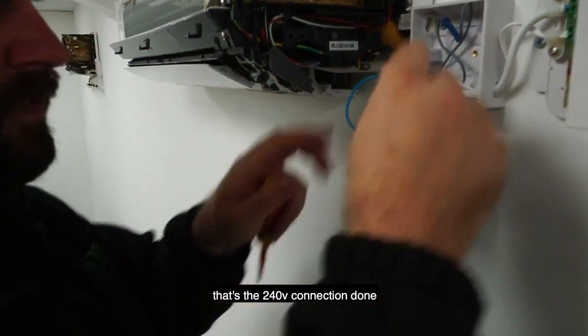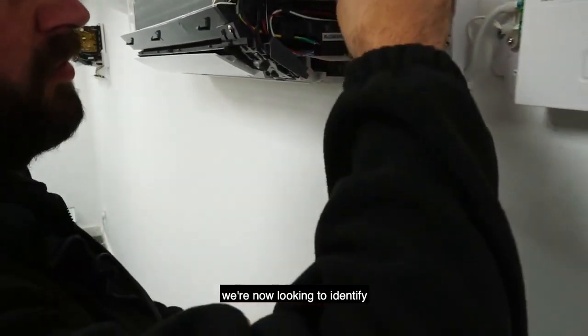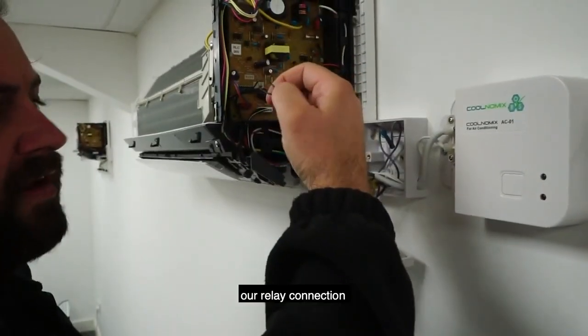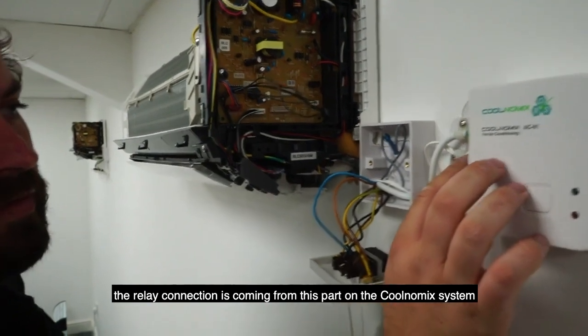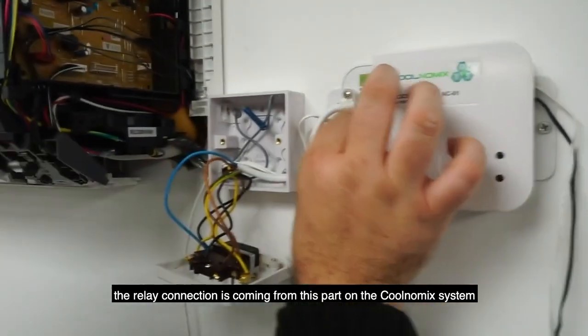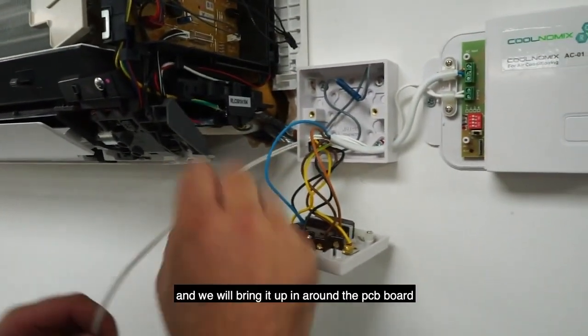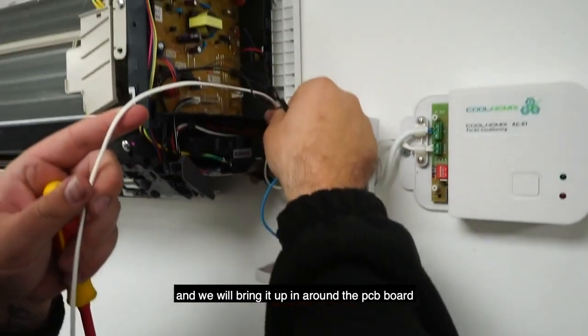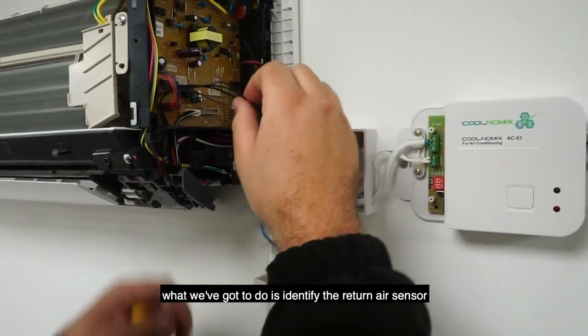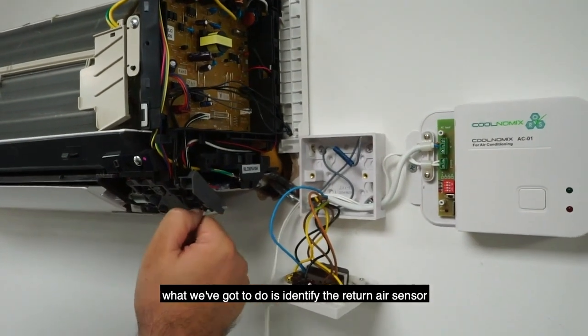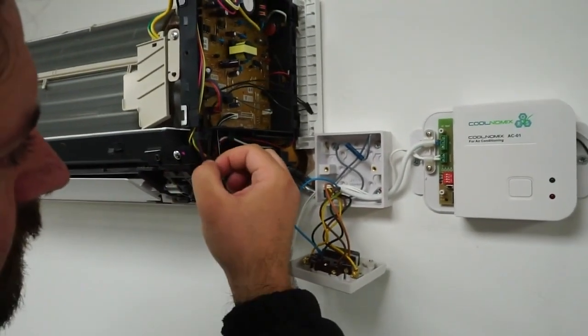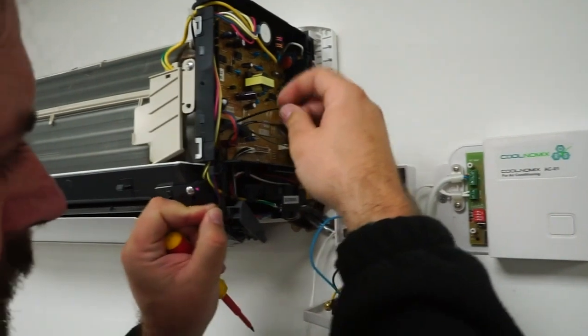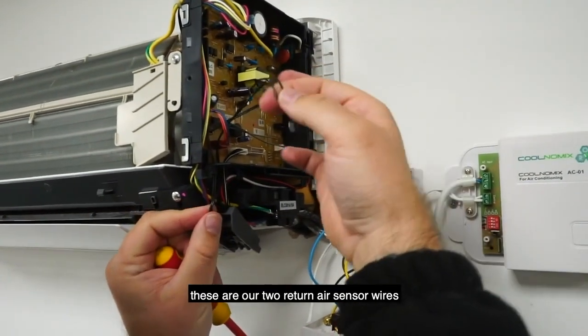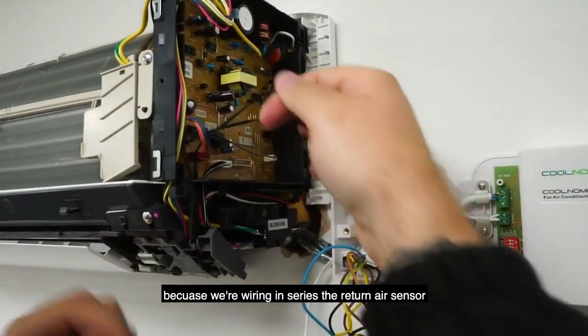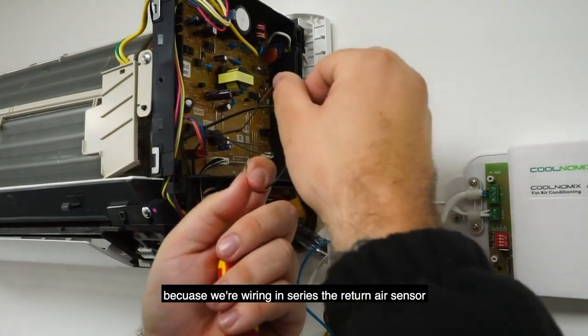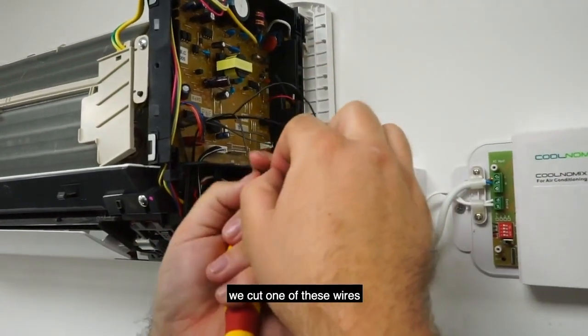That's a 240 volt connection done. We're now looking to identify our relay connection. The relay connection is coming from this part on the Coolnomix system. Cable's coming through, and we'll bring it up in around by the PCB board. What we've got to do is identify the return air sensor and find out which cable it is. So on this particular system, these are our two return air sensor wires. Because we're wiring in series to the return air sensor, we cut one of these wires.